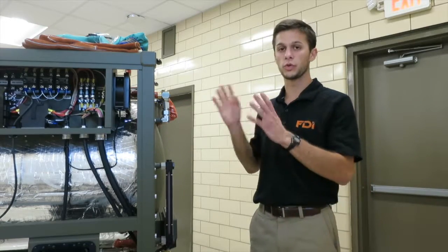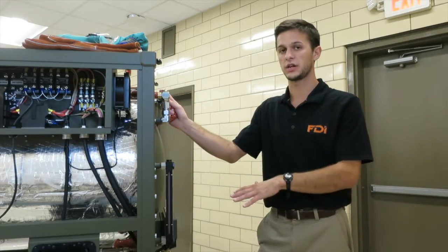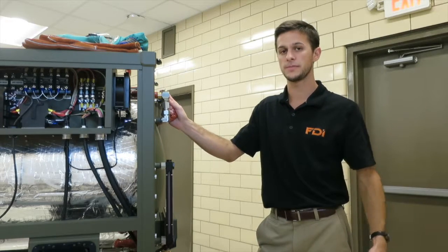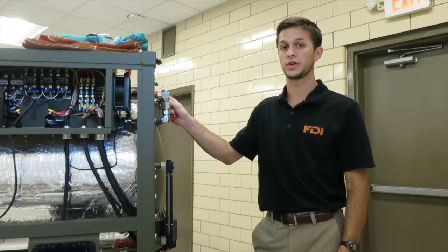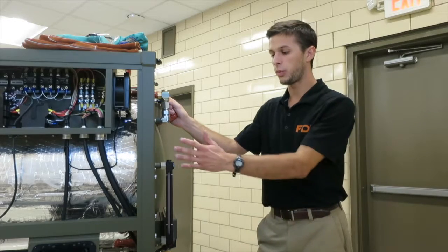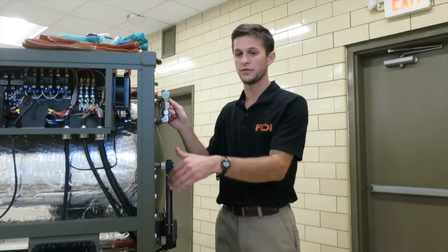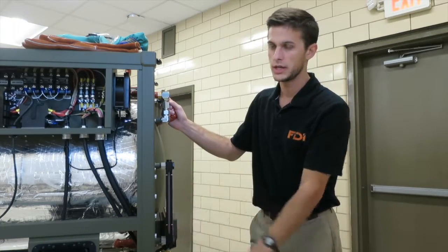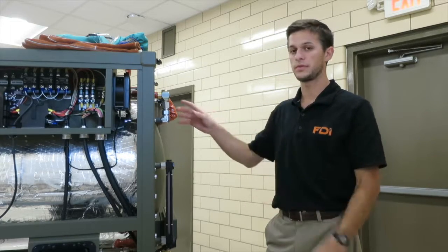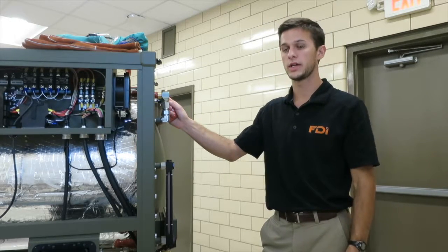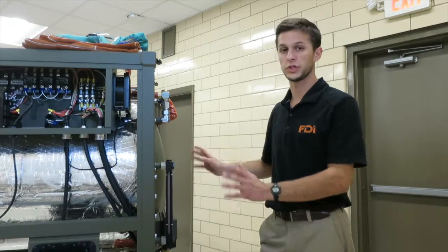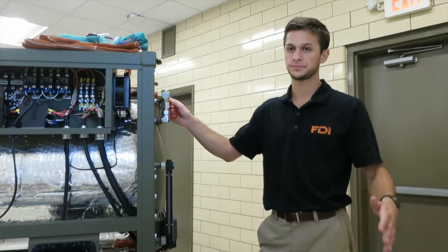Also, as a general rule, always fully drain the sterilizer main unit and the water recovery system if it's not going to be used for an extended period of time. If you keep water in there, there's going to be a lot of biological growth, some algae. So just to keep the biological growth from growing, remove and fully drain all the water from both units.